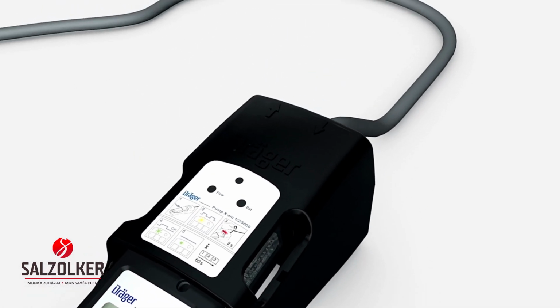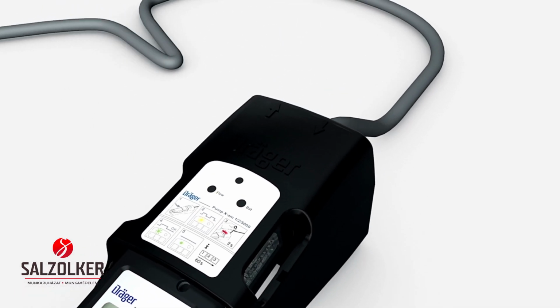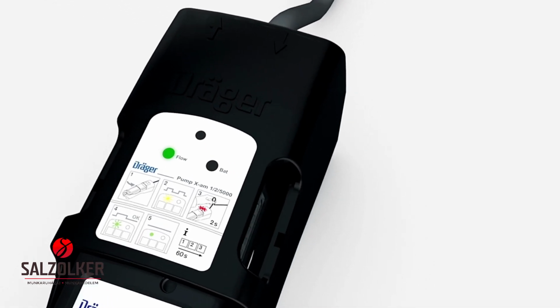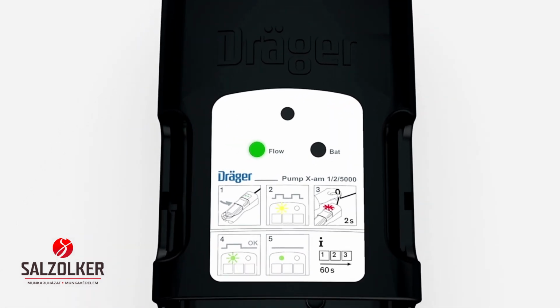Now close the intake connection by kinking the hose for 2 seconds. The flow LED flashes red and a continuous tone can be heard. Now release the intake connection. If the LED lights up green, the device is ready to use. You can now start measuring. If the test is unsuccessful, the flow LED flashes red and a continuous tone sounds.